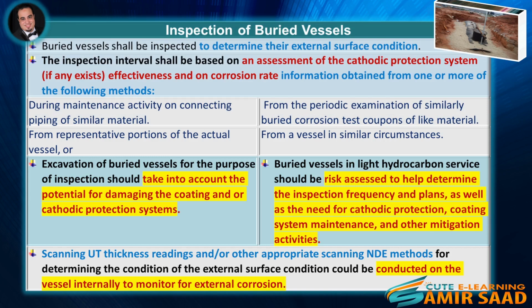Inspection of buried vessels. Buried vessels shall be inspected to determine their external surface condition. The inspection interval shall be based on an assessment of the cathodic protection system, if any exists, its effectiveness, and on corrosion rate information obtained from one or more of the following methods.